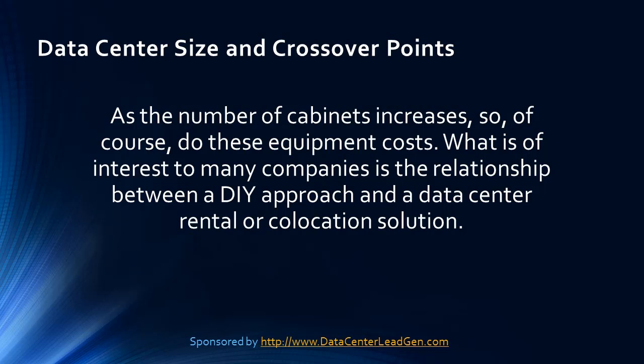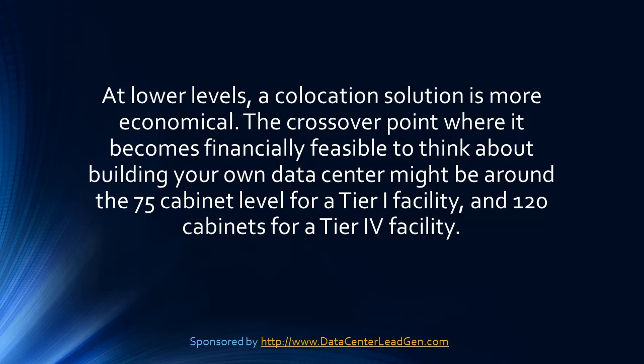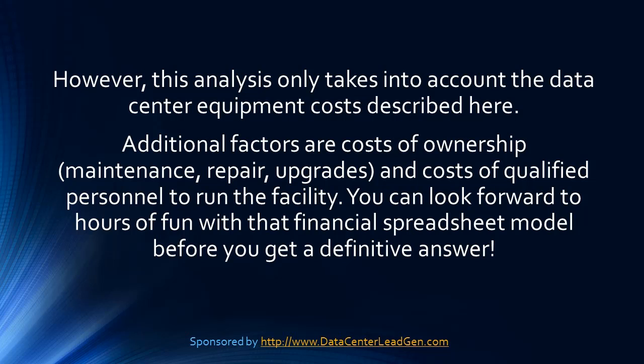Data center size and crossover points: as the number of cabinets increases, so do these equipment costs. What is of interest to many companies is the relationship between the DIY approach and a data center rental or co-location solution. At lower levels, a co-location solution is more economical. The crossover point where it becomes financially feasible to build your own data center might be around 75 cabinets for a Tier 1 facility and 120 cabinets for a Tier 4 facility. However, this analysis only takes into account the data center equipment costs described here. Additional factors include costs of ownership, maintenance, repair, upgrades, and costs of qualified personnel to run the facility. You can look forward to hours of fun with the financial spreadsheet model before you get a definitive answer.